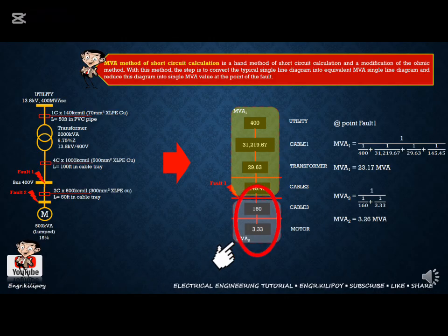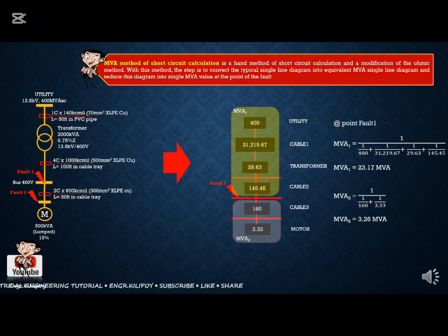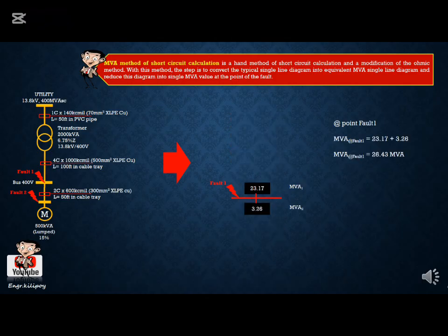And for your MVA 2 value, this one is in series connection. So this is how to calculate it when it comes to MVA simplification. So MVA 2 is equal to 3.26 MVA. So na-simplify na natin as to this value. Yung upper side, upstream, is 23.17 as calculated, and yung downstream, in between fault point, is 3.26 MVA. So, kapag nakakita ka ng ganitong connection, it is simply adding two values like series connection. So at fault 1, MVA will be equivalent to 26.43 MVA. So meaning at fault point 1, ang total MVA short circuit natin is 26.43 MVA.